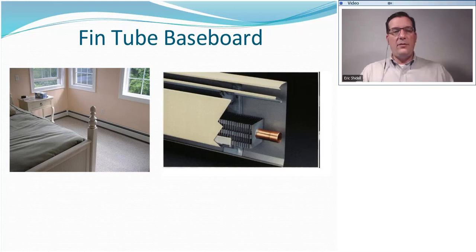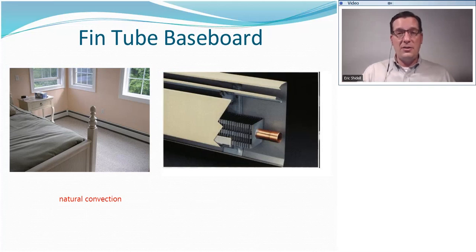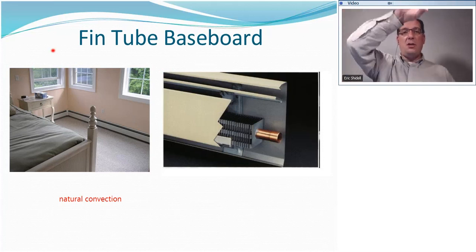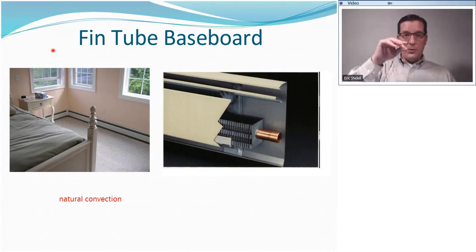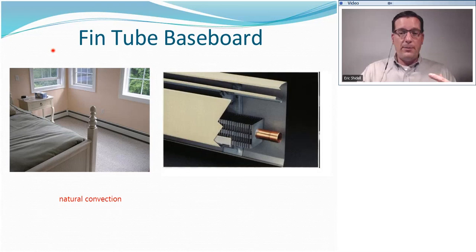Natural convection is different than forced convection, hence forced air, right? Natural convection is also called gravity circulation because cool air is heavier and it falls toward the floor, and then the warm air that's heated by the convector rises up, and we get this nice, gentle, circular flow of air through the room. In order for fin tube baseboards to do their best work, they have to be free from obstructions. We don't want the drapes hanging down over the front of the radiator. They need to stop short of where the opening on the baseboard is.